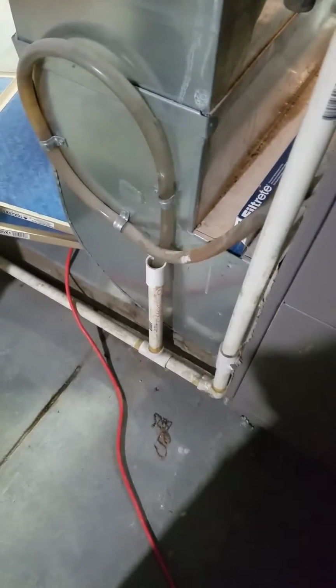There's your condensation line running in and over, and your tubing runs through the furnace and goes right there right now. So that'll change when you've even got a little lip to put your condensate pump on right there if you need be. One of the issues that I don't like, let me try to get up here, there's a little saddle tap valve right there, and it runs over copper tubing where this unit used to have a humidifier. And what happened was, when they went to take that old humidifier out, they just left the tubing and crimped the end right there. And so that puddles water down on the floor, and it's puddling water from the saddle tap down to the floor right here. And we want to get rid of that.